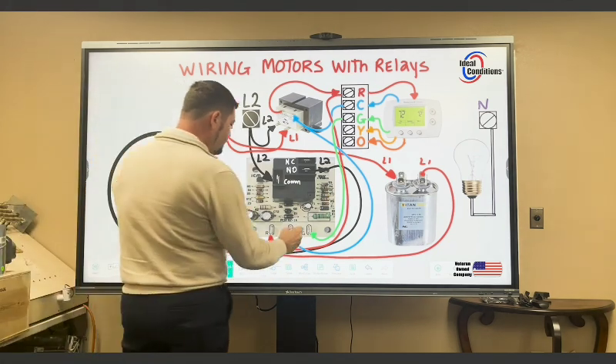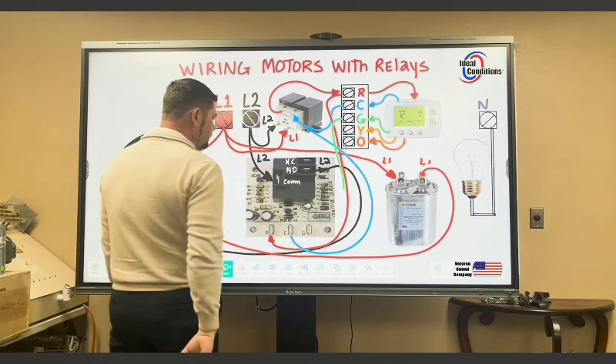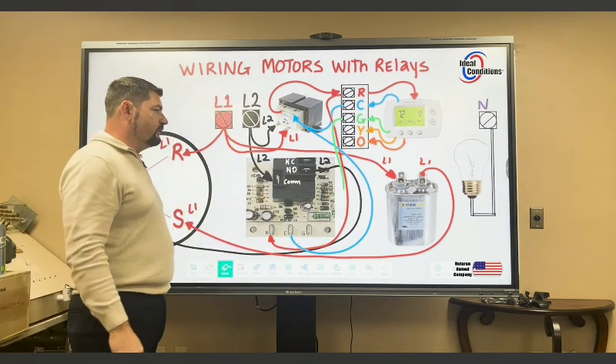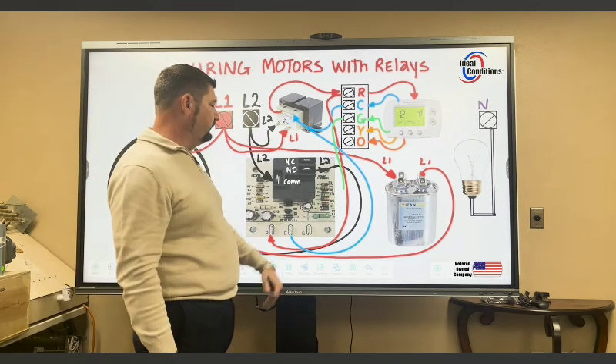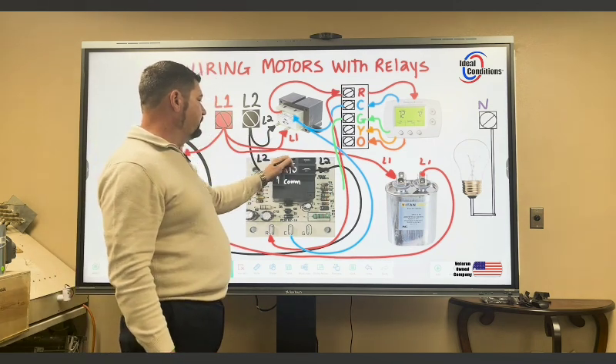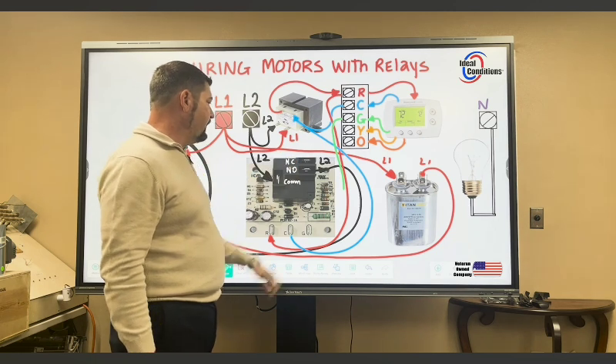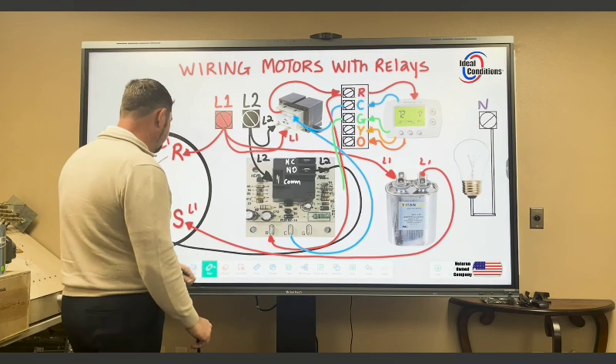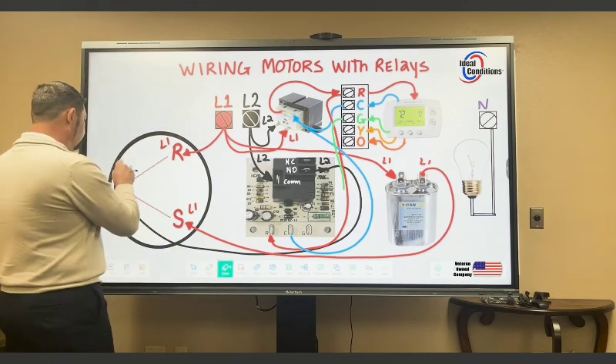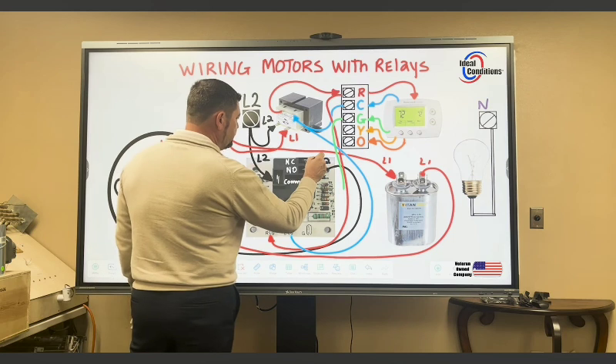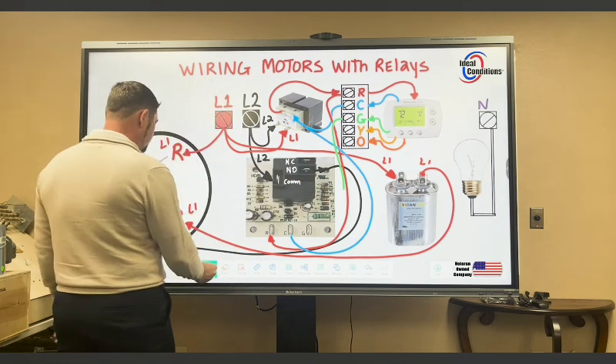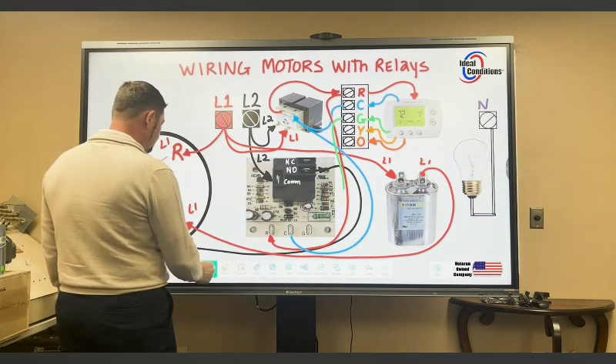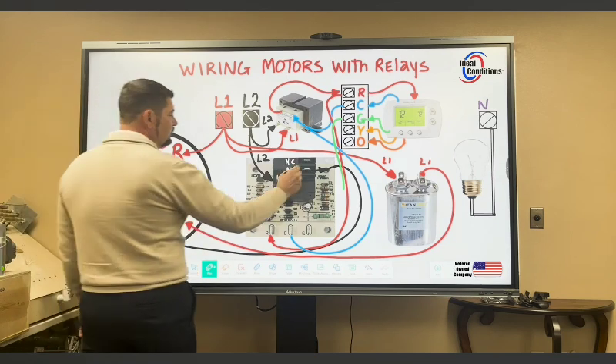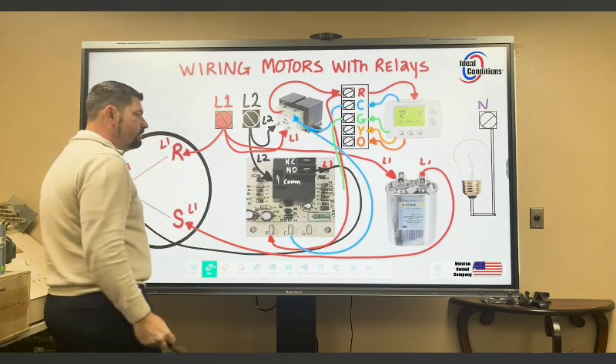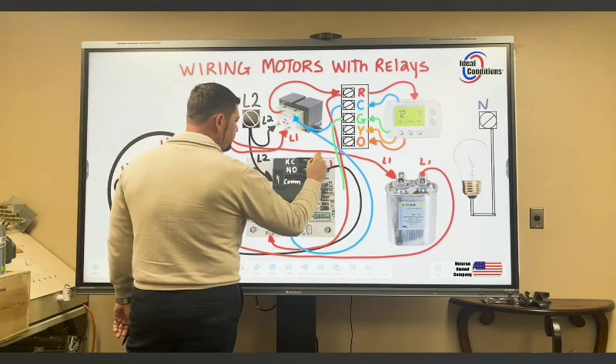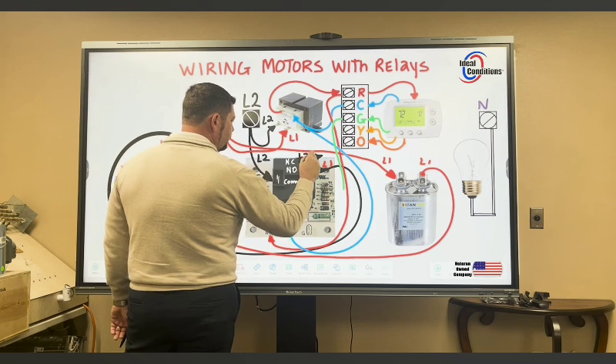Now the moment we take our G call away, L2 is still going to be present there for a 50-second countdown. Once that 50 seconds is up, power will now be present on the normally closed portion, and this will go back to L1. So we're going to go ahead and draw that back, and we're going to say L2 will no longer be present here. After 50 seconds, it'll no longer be present there. What will be present is L1, but L2 is still going to be present over here on this top portion. I'm going to draw another arrow, and we're going to label that L2.